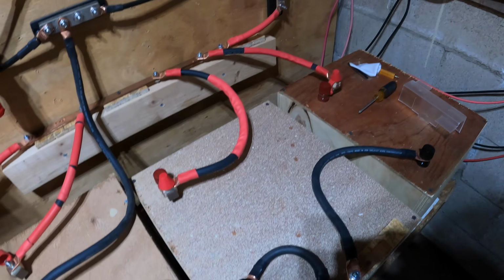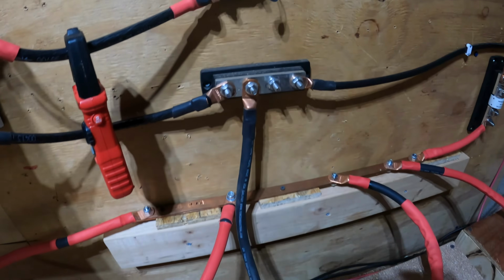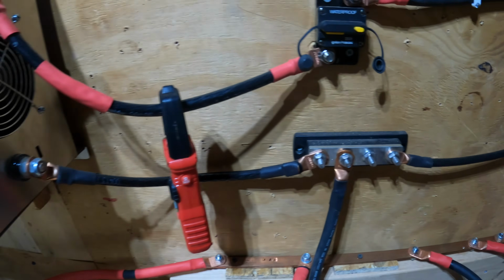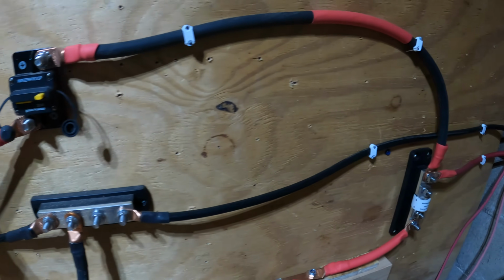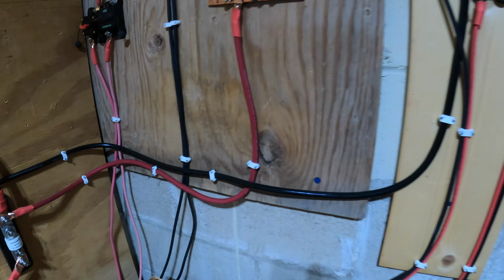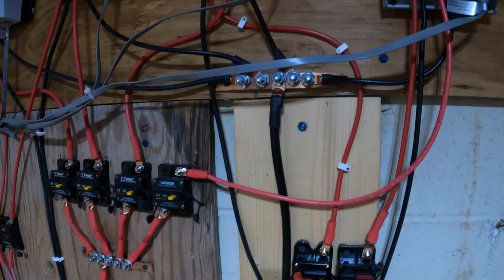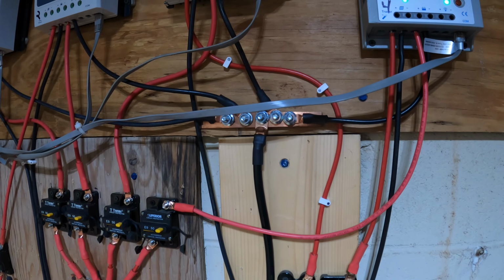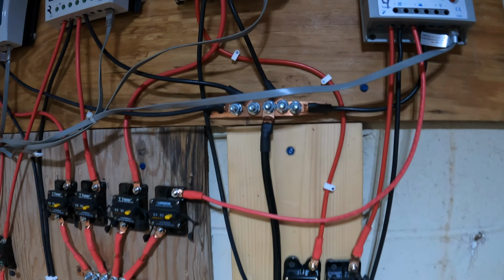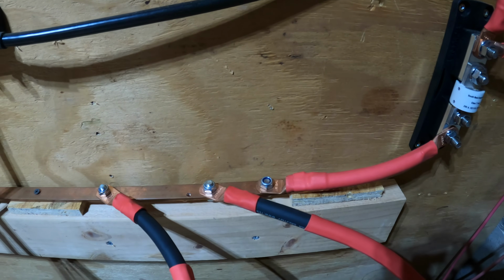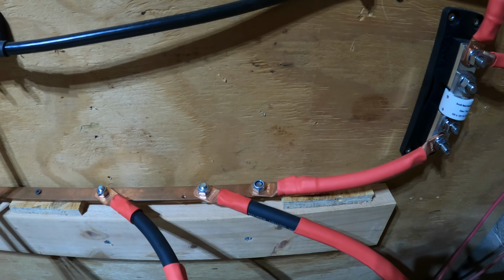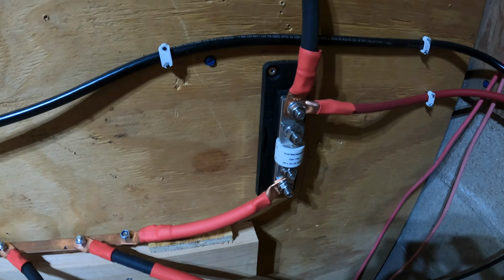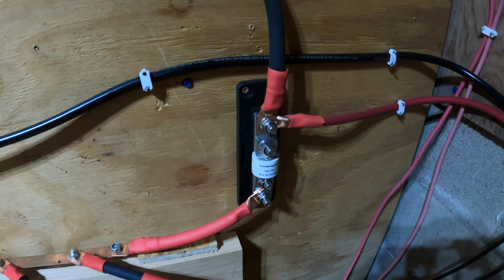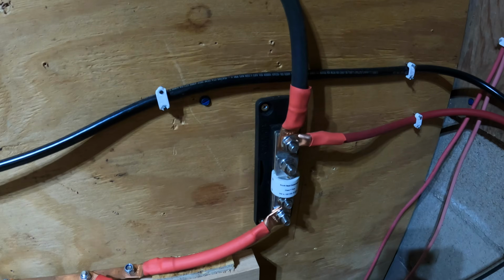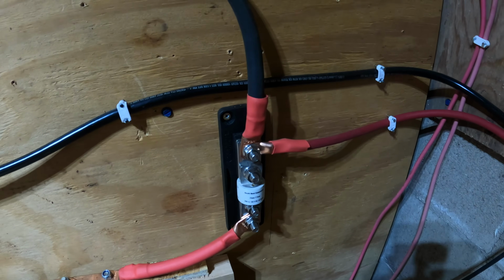The battery bank on the negative side just comes up to this bus bar, and then the inverter is wired to that bus bar. On this side, the negative goes back into here, connects to this bus bar, and that bus bar distributes out to my 4 charge controllers. On the positive side, I have a heavy gauge wire going from my bus bar to my Class T fuse. The Class T fuse separates the bus bar from the general system, so if there's a problem, that'll shut everything down.